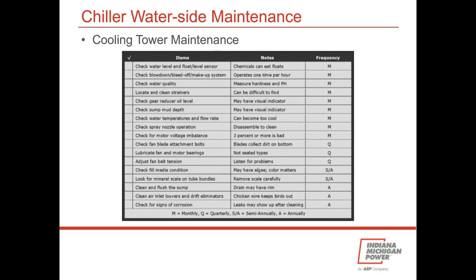It's typically conducted during cold weather months, including often holidays, on an annual basis, and it really takes time. It usually takes 4 or 5 consecutive days. For instance, day 1, you'll drain the sump, cooling tower floor, and let it dry. Day 2, you might wash down the tower walls and filter media and then let them dry. Day 3, you might clean coils and adjust or replace fan drive belts as needed. And day 4, then you're refilling the sump after cleaning's completed and you're checking for leaks.